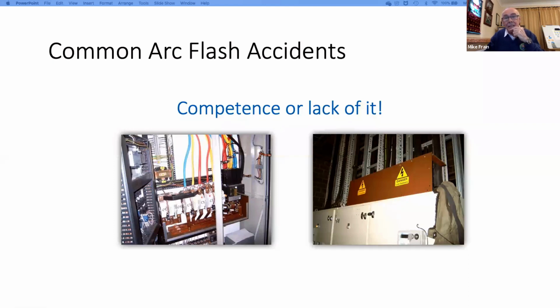So you think that was it. The seriousness of it actually was compounded by the conversation I had with a young man who was working inside the same panel. He was undertaking some diagnostic testing with a multimeter on the bus bars while they were energized. Above the bus bars, but while the bus bars were energized. He told me that he worked for a refrigeration contractor who had a contract for the fridge plant at that facility. And on further questioning, it transpired that he had very little experience. At the height of his qualifications, he had a National Vocational Qualification Level 2, which is fairly low for those people outside the UK. So he should not have been there. He wasn't competent for doing anything on electrical systems at all, in my view, and he hadn't got the experience or the qualifications or knowledge.